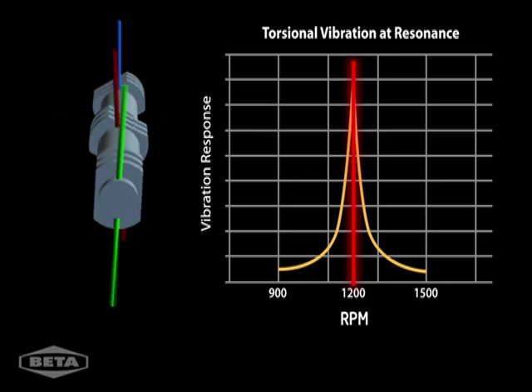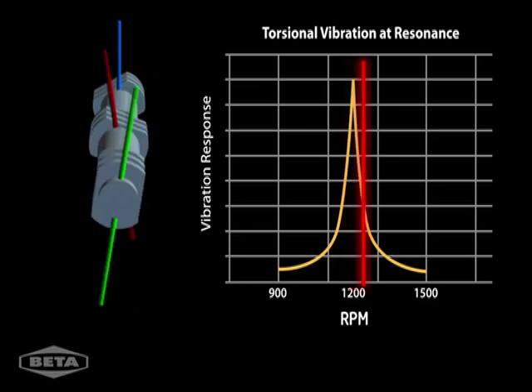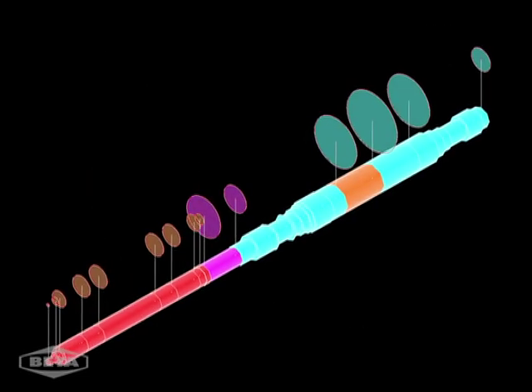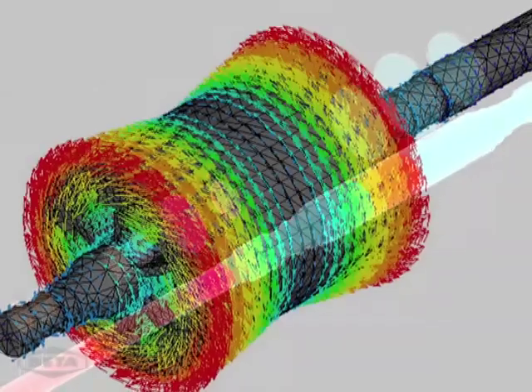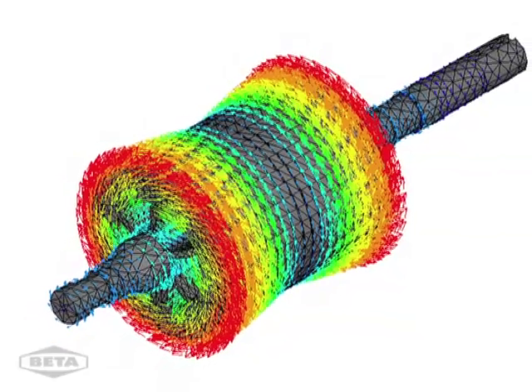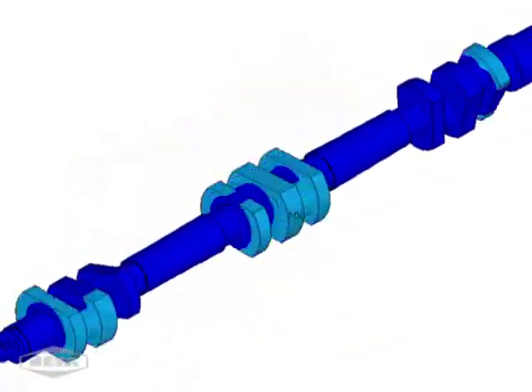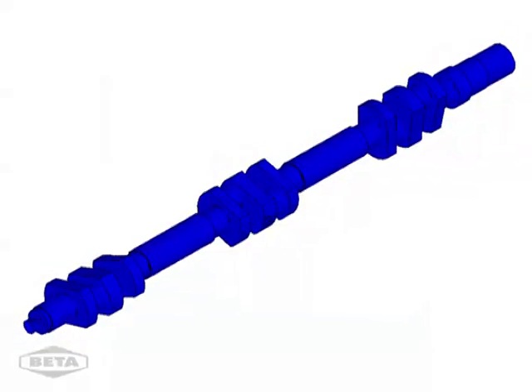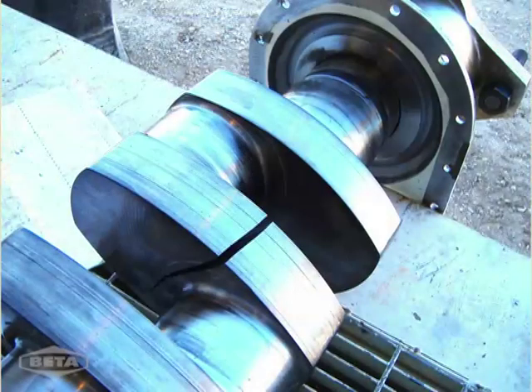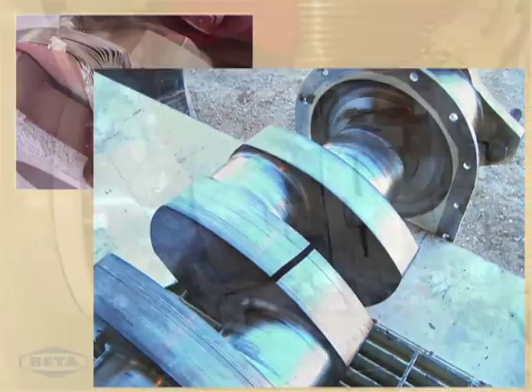At resonance, the vibration response is greatly amplified. Above the resonant frequency, vibration response is significantly reduced. The torsional analysis must accurately predict resonant conditions and vibration problems; if not, the results can be catastrophic — destroyed couplings, broken compressor shafts, and broken motor shafts.